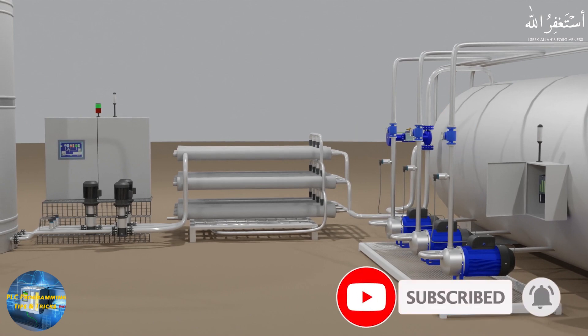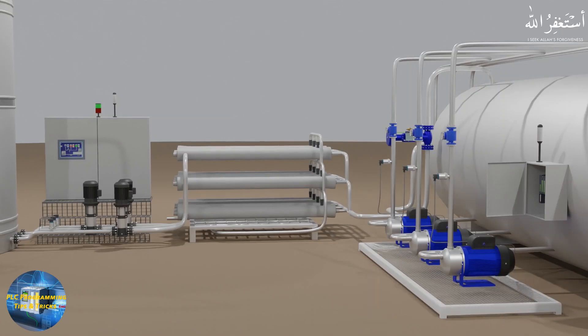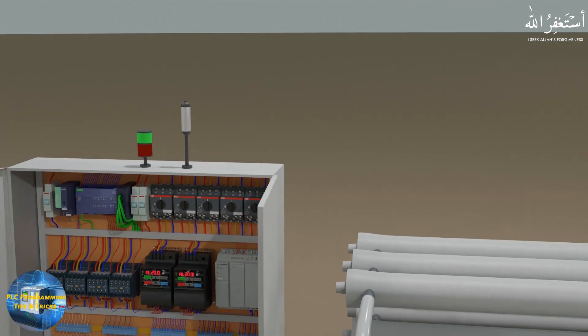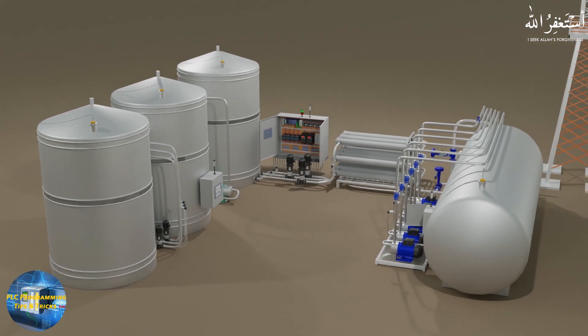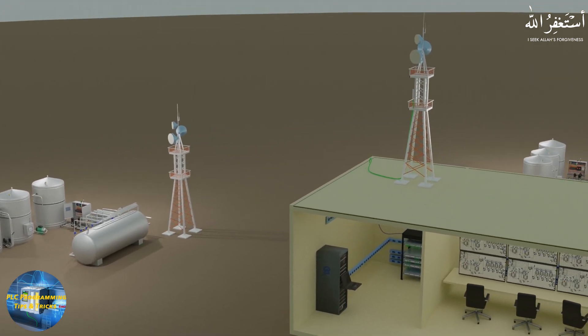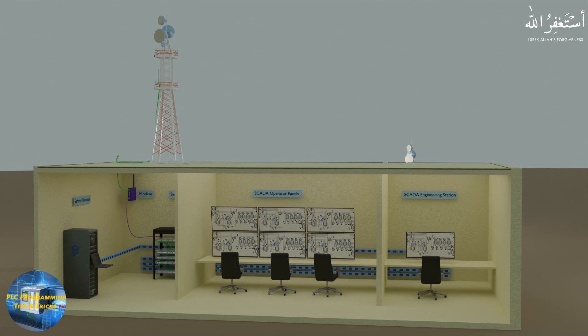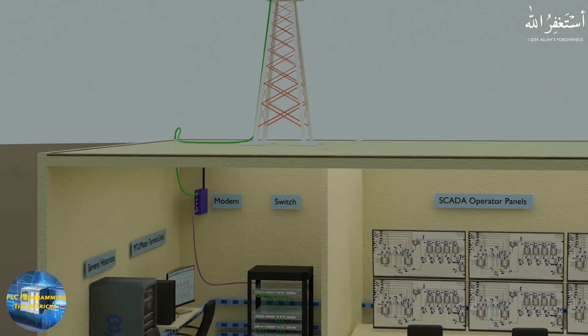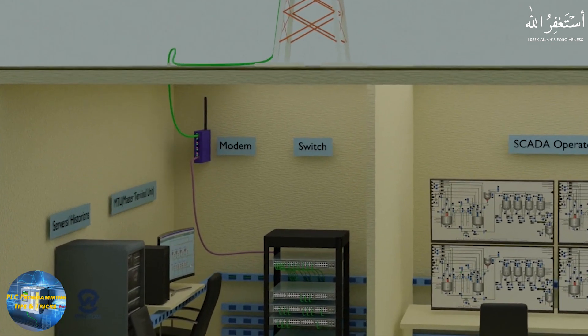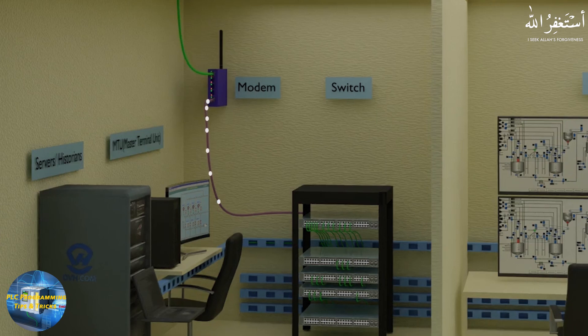The PLCs and RTUs transmit their process data to a central control station. At the central control site, this data is received by a communication tower in the form of radio waves. The data then comes into the SCADA control room where it is converted to Ethernet using a modem. The modem converts the radio wave signal to Ethernet so that data is available for all devices inside the SCADA room, and it is connected to an Ethernet switch — a central hub where all devices share data with each other.